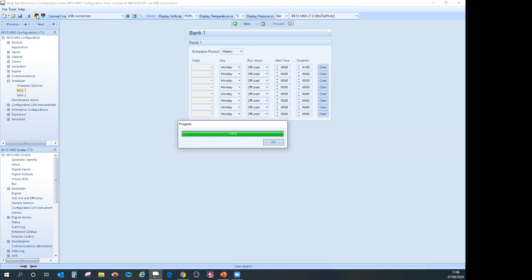You can read from the controller whenever you like, even when it's running, but you can't write to the controller unless it's actually in stop mode, because writing basically power cycles the controller - it stops the controller and writes all the information back to it. So that's now written to the controller, and I've made my changes.